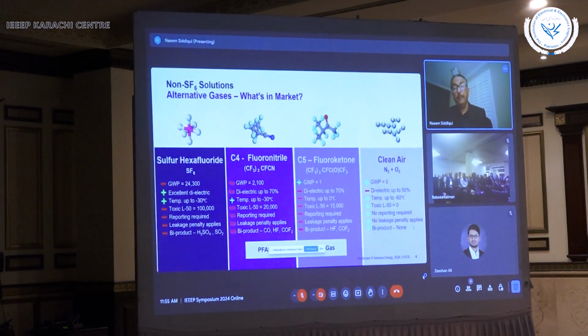an insulation medium. So 10, 15 years back, this discussion has started, and what's in market was like we have on the left side you can see SF6 gas, and in the middle basically two C4 and C5 insulation gases. These are 3M manufacturer who is the producer of these insulation gases, and more or less C5 somebody is using it, but C4, which is fluoronitrile, is still in use as a mixture to use as an insulation gas. But whereas basically clean air is the Siemens energy technology, and not only Siemens energy but also other manufacturers also basically working with using clean air as insulation medium as well. So mainly basically we have fluoronitrile mixture an option, and also clean air as an option also.